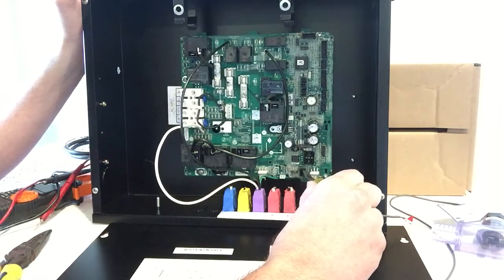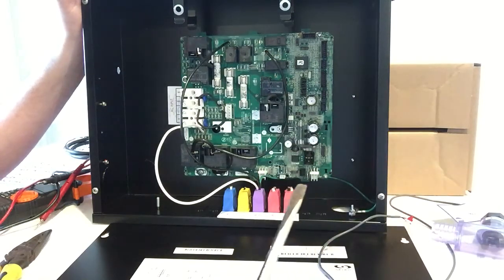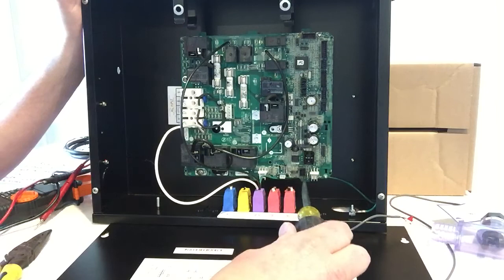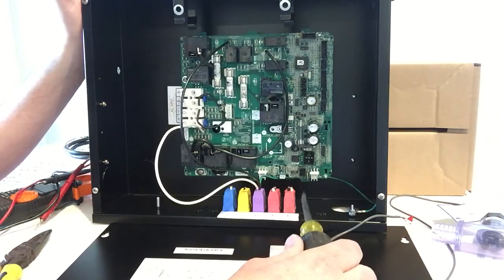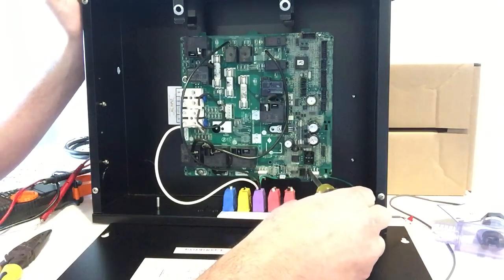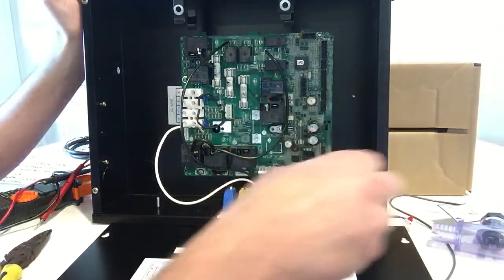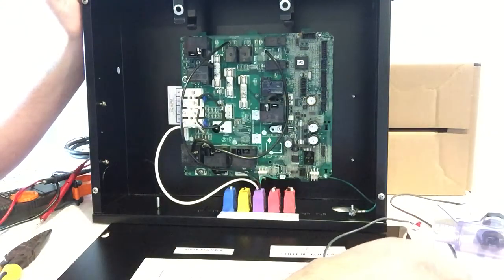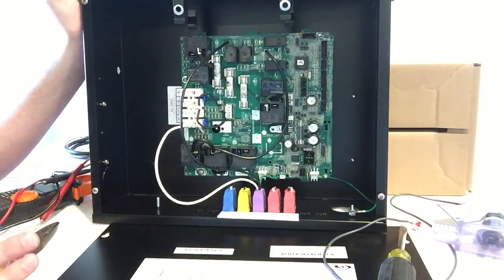Now when you do this, if you hear a click, that is your heater turning on and the error code goes away on the screen. That is telling you that your flow switch is the problem. Now, sometimes people get scared, they don't want to stick a screwdriver on a live PC board. It's low voltage, it's not going to get you, but if you touch something else, it will.